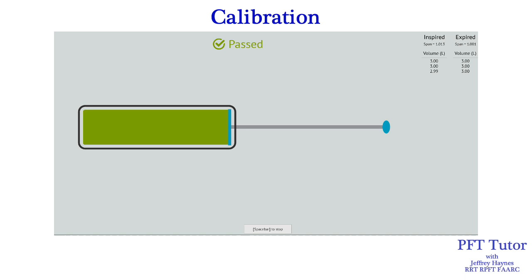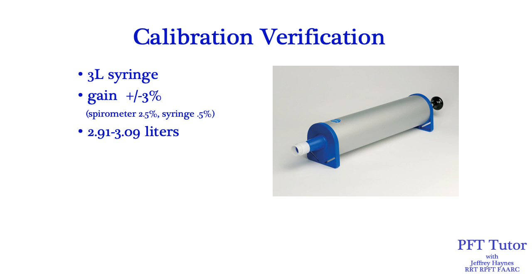Calibrating is adjusting the machine so it will read the desired target. According to the American Thoracic Society and European Respiratory Society standards, an acceptable calibration verification with a 3-liter syringe should read 3 liters plus or minus 3%. There's a 2.5% error for the spirometer and a half percent error for the syringe, so cal verifications should read between 2.91 and 3.09 liters.